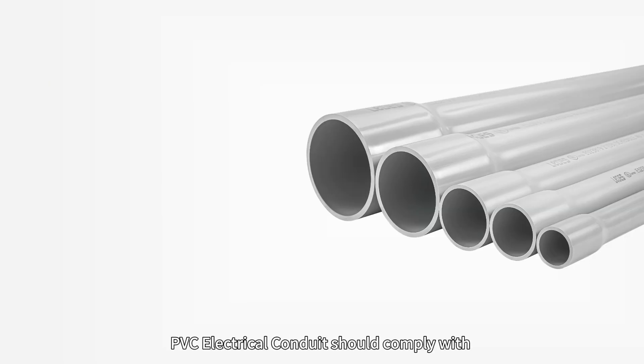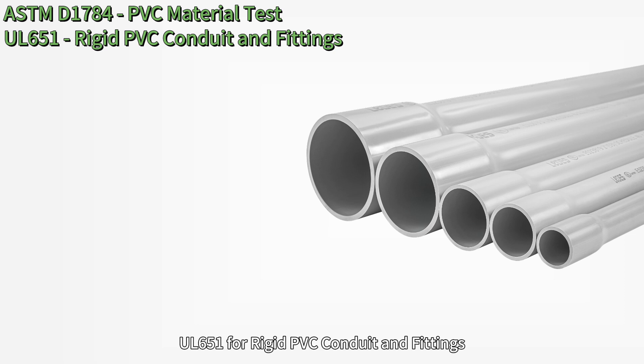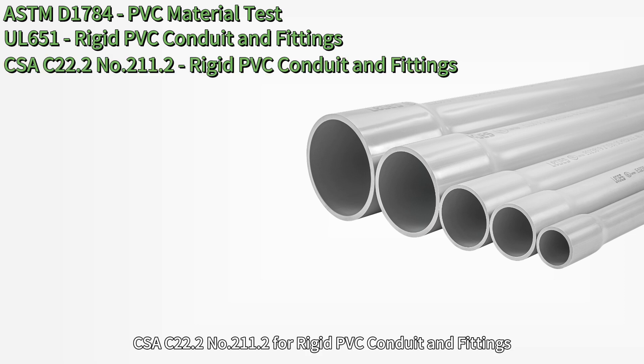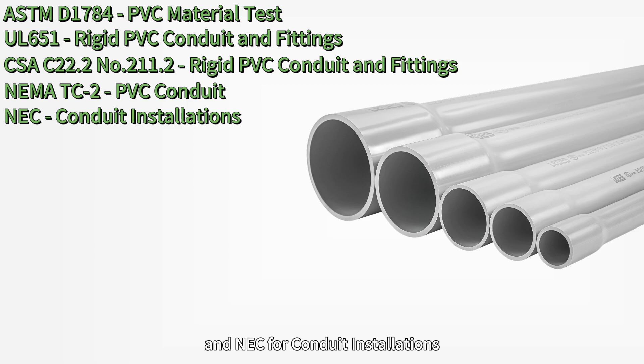PVC electrical conduit should comply with ASTM D-1784 for PVC material testing, UL-651 for rigid PVC conduit and fittings, CSA C-22.2 No. 211.2 for rigid PVC conduit and fittings, NEMA TC-2 for PVC conduit, and NEC for conduit installations.